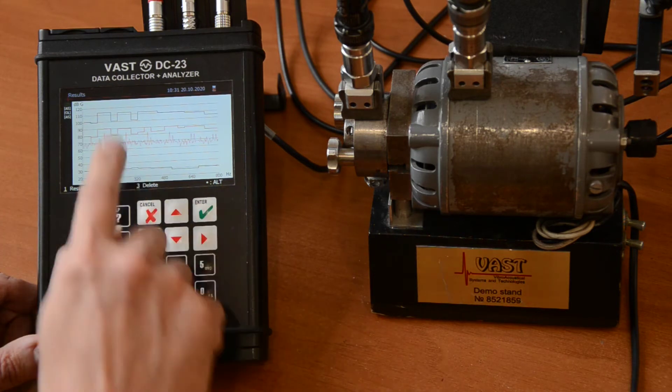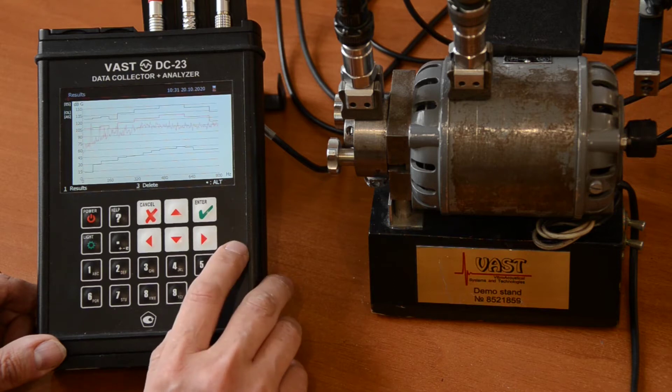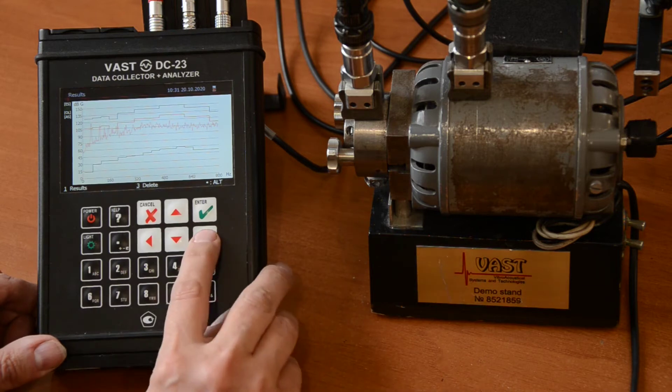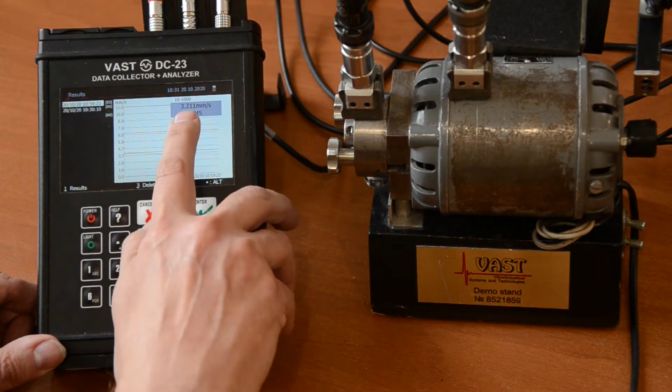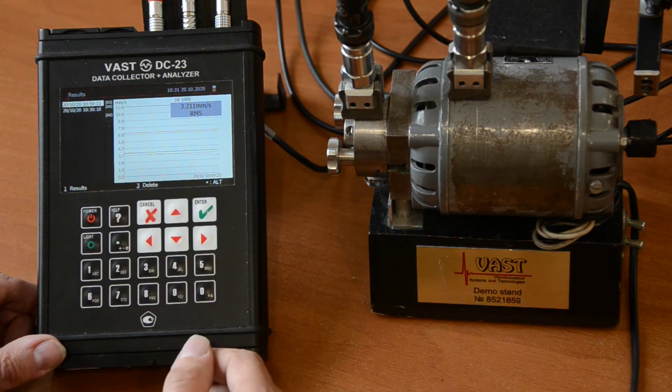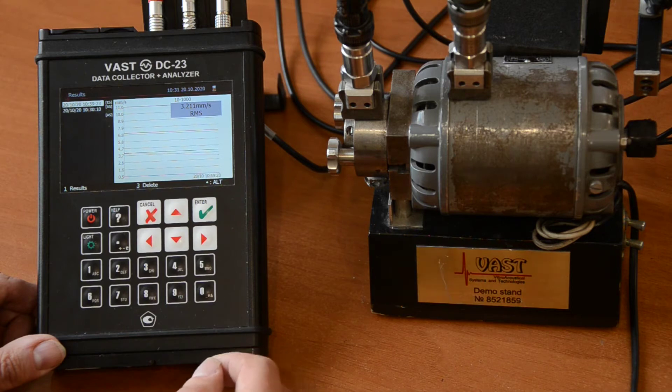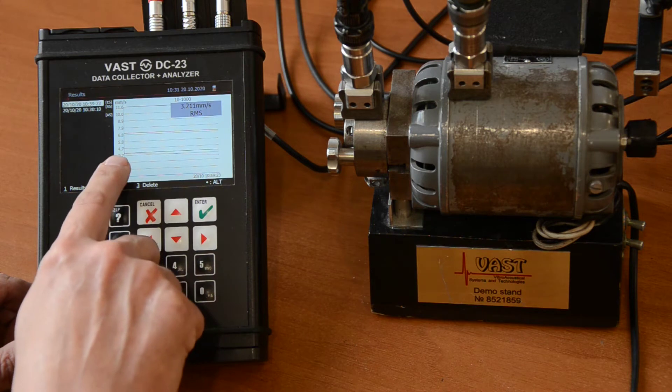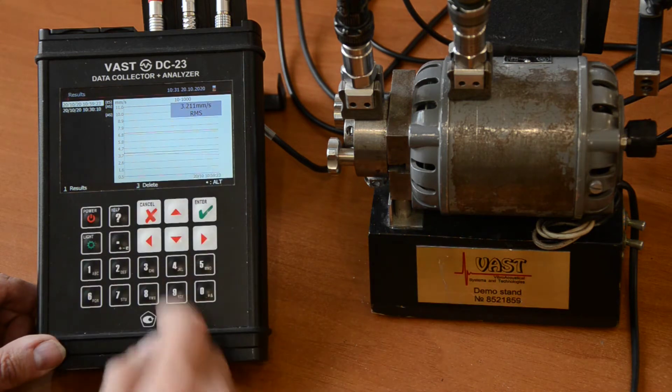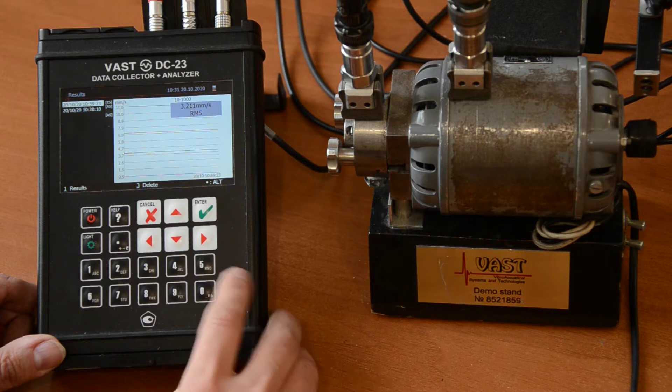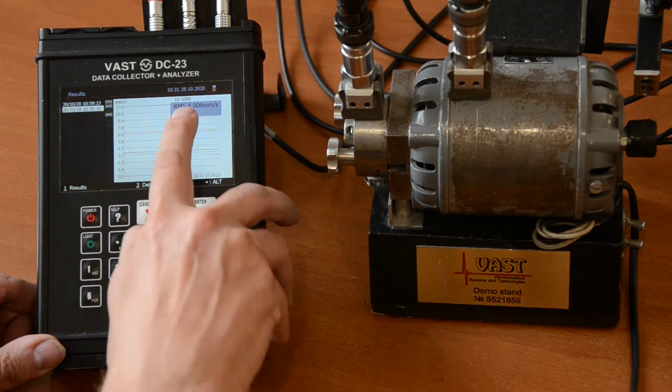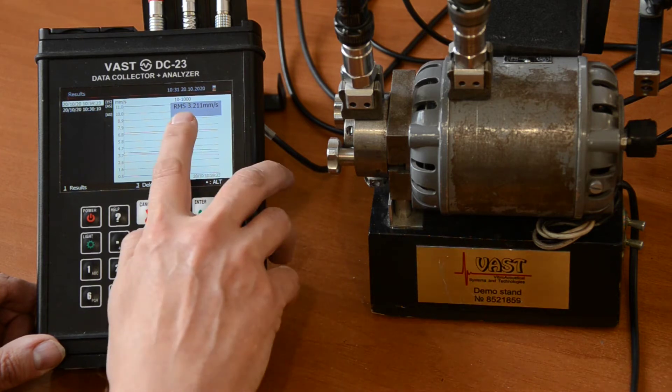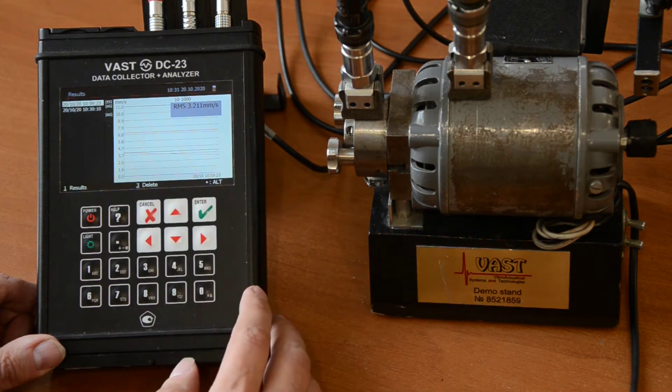So this is the envelope spectrum. This is the auto spectrum, and you also see that we have some alarm levels. This is overall level, and this is the overall level in this frequency band. So this is 3.2 mm per second RMS in 10 to 1 kHz band. And we have two measurements here. The previous one was 3.7, and now we have 3.2. So we have a little bit of a decrease in overall level. And we can also see the previous one.